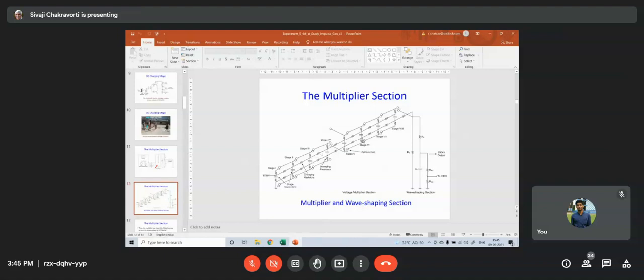But now we have to discharge it. Now there are a lot of options. I can discharge all the capacitors in parallel, then the energy remains the same, but the voltage is only the voltage of one capacitor because all are in parallel. So we can't get more than 175. In this particular diagram, you can see four capacitors are in parallel, another four are in parallel, and they will be connected in series during discharging, so that we get 175 plus 175, 350 kV as the output.